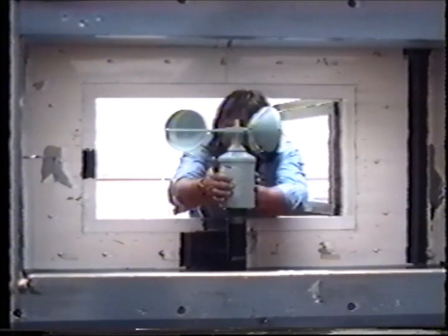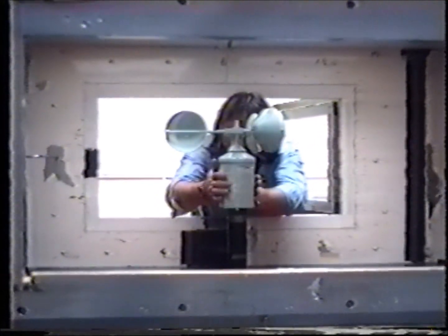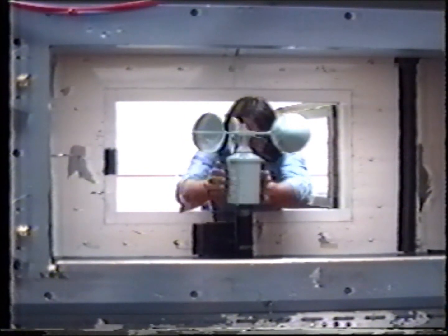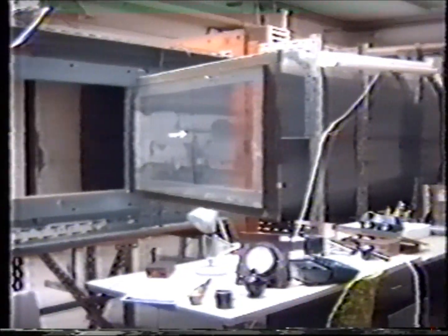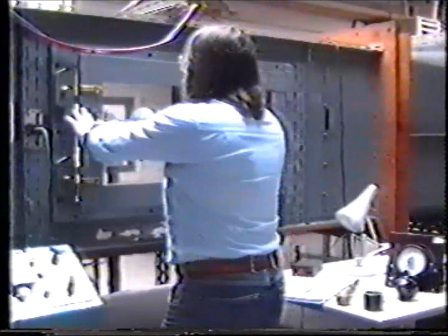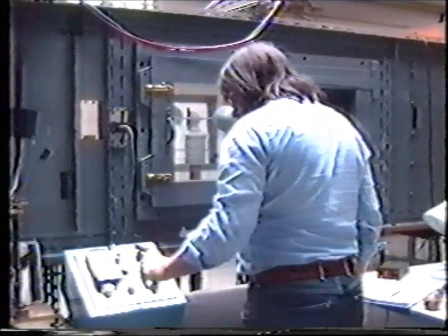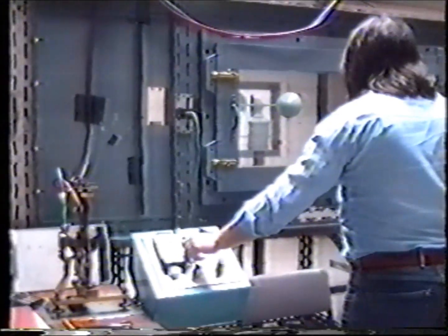The anemometer to be calibrated is fixed firmly into a post in the working section and connected to a frequency counter and voltmeter to monitor the output. The wind tunnel dates from 1952 and was formerly located at Harrow before being moved to Bracknell in 1960. It is capable of producing accurate wind speeds up to 80 knots and is of the open loop configuration.